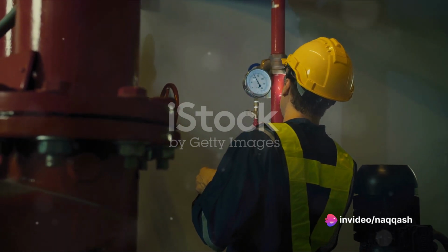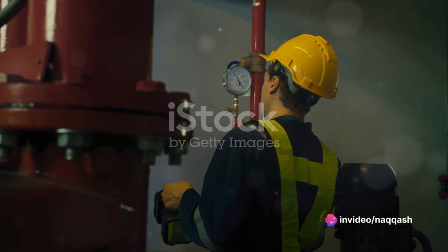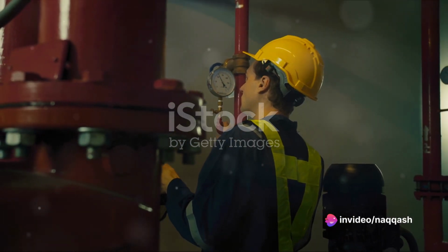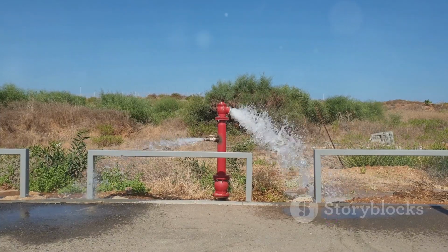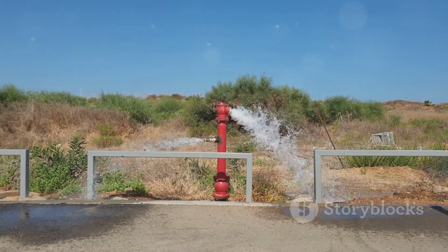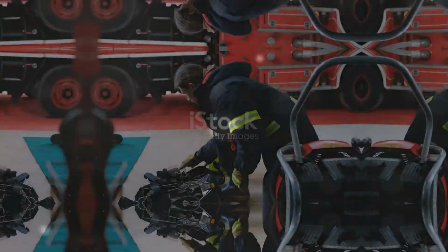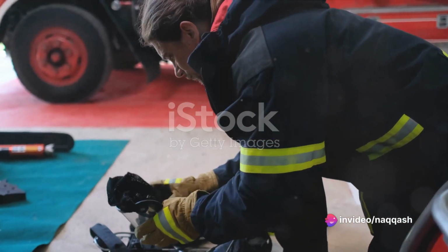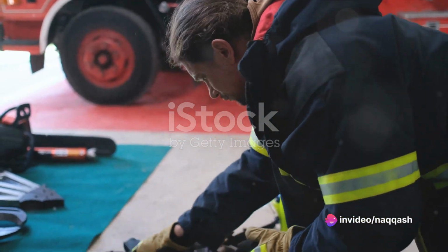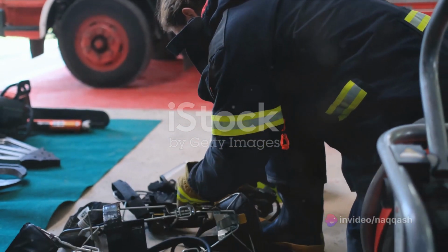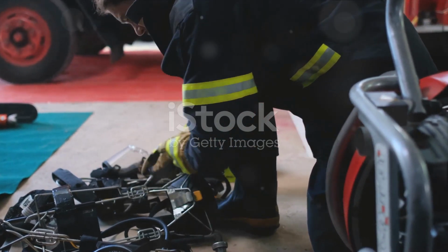This is a crucial decision as the pump must meet the specific requirements of the building it will serve. The pump must be able to deliver the correct pressure and flow of water to the fire sprinkler system. Once the right pump has been selected, the next step is to prepare the pump room. This space should be clean, dry, and well ventilated. It should also be easily accessible for maintenance and testing purposes.